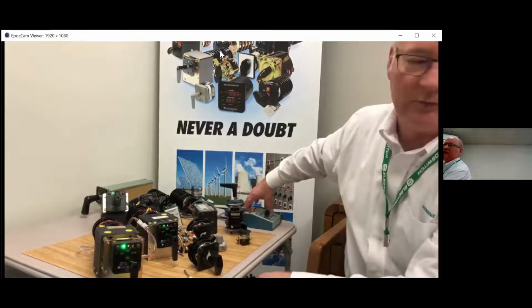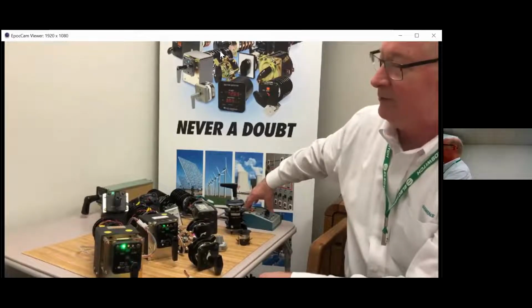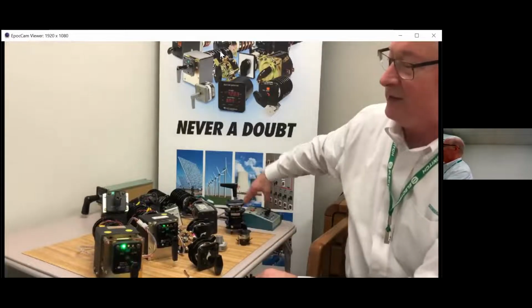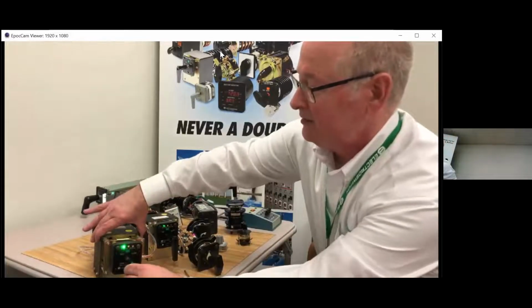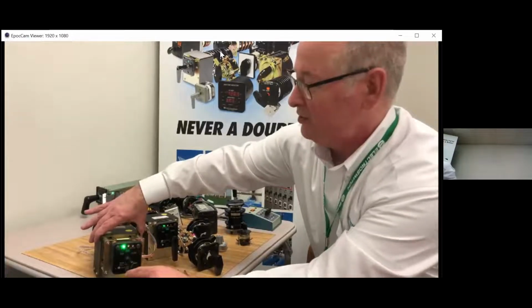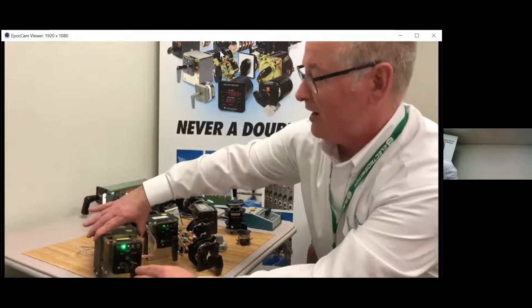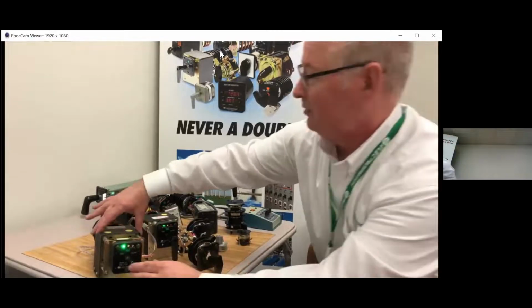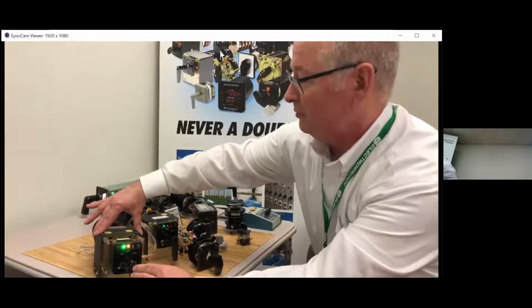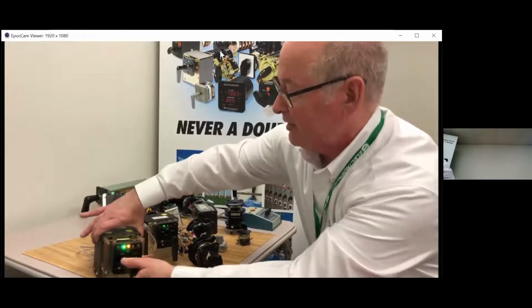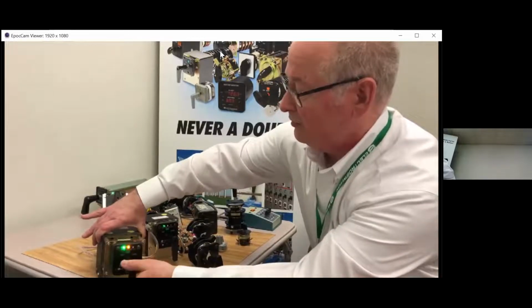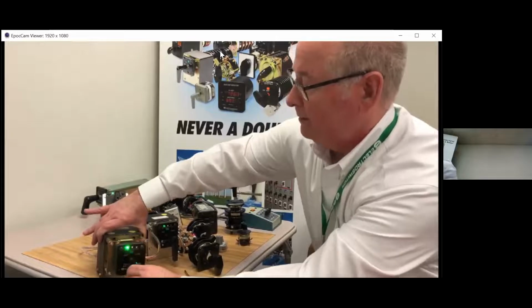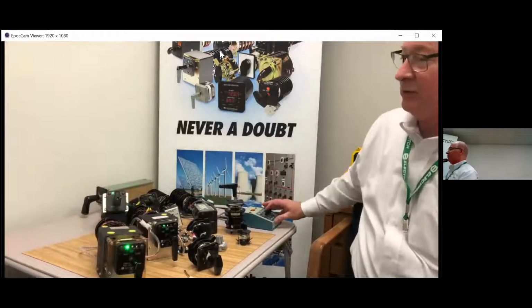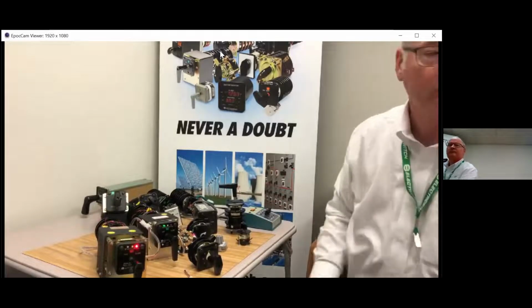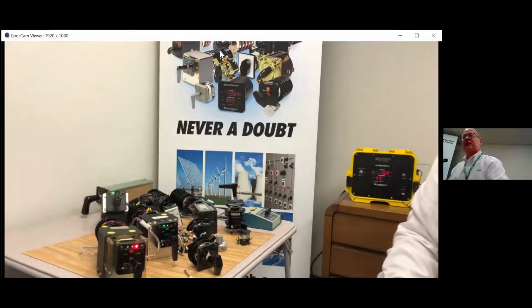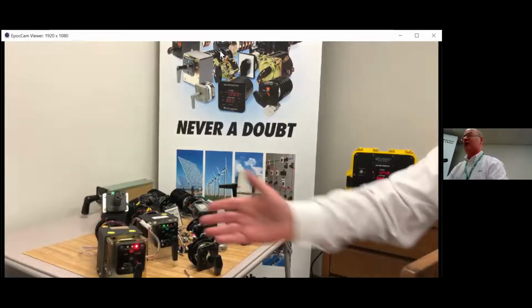And you'll see the spring return on the lockout relay, allow it to come back to the manual position. But you can then see how the lighting and the LEDs, they're pretty bright, and so you can see them from a lot of different areas within the substation, as well as providing SCADA control or local control. And I push this in, my amber light comes on, and I can manually trip and close the breaker with the handle. In my remote mode, I can do it remotely. So that's kind of a basic functionality of a lockout relay, manually as well as electrically.